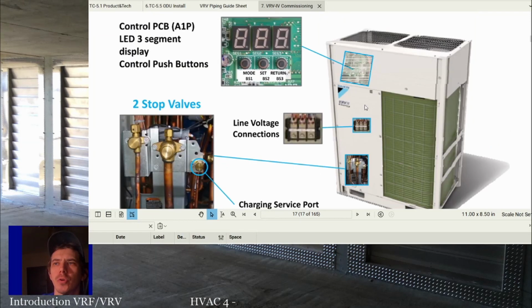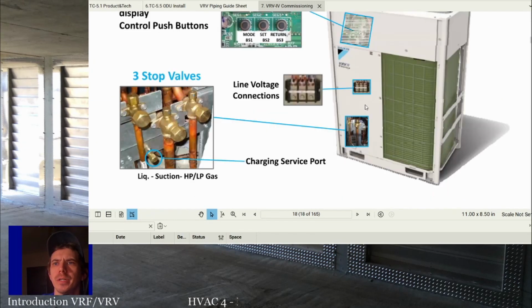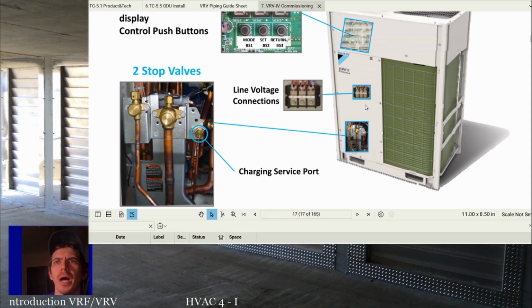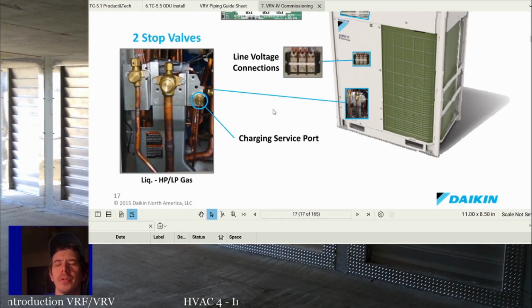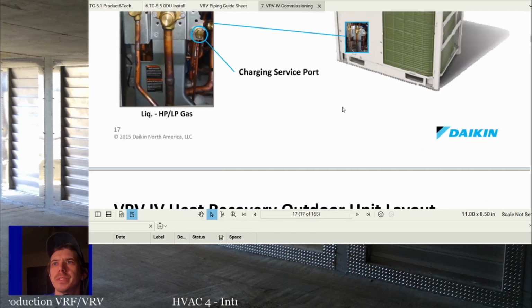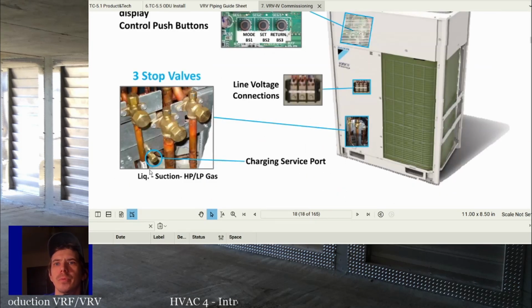There's controller connections in here too, that I don't see. But here's a good picture of the three pipes, right? The three pipes that come out of the outdoor unit. So again, liquid, high pressure, low pressure, yeah. Oh no, is this a heat pump? No, no, heat recovery. This is what we want. Liquid, suction, high pressure, low pressure.